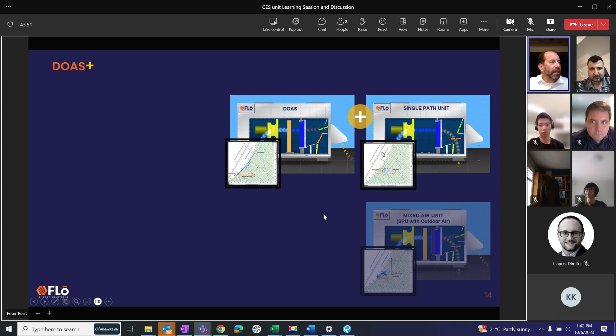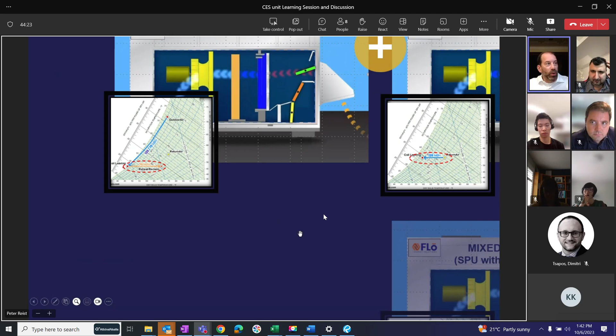you see that you've got your DOAS that's cooling and dehumidifying, then it's reheating. And over here, you've got this single path unit that's putting in energy to cool. And these two things are going in opposite directions. And whenever I see things working in opposite directions from a psychrometric standpoint, I see opportunity because in some ways there's waste here. This RTU is cooling the reheated air coming off of this DOAS.